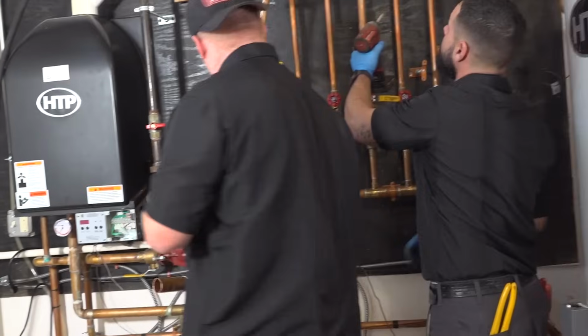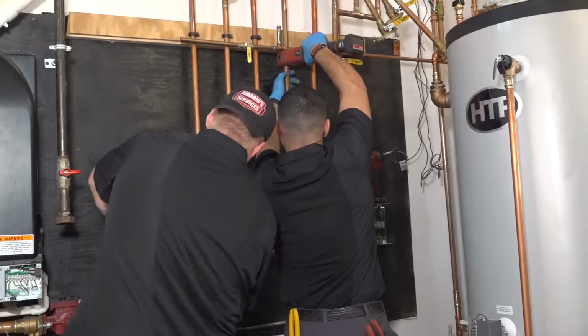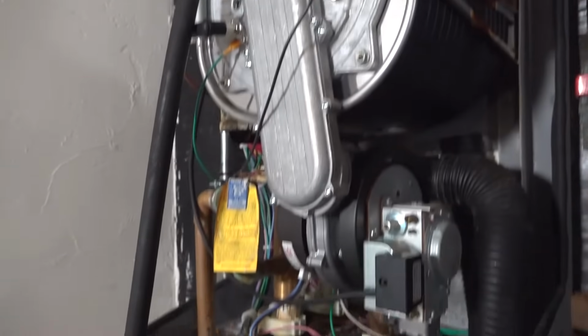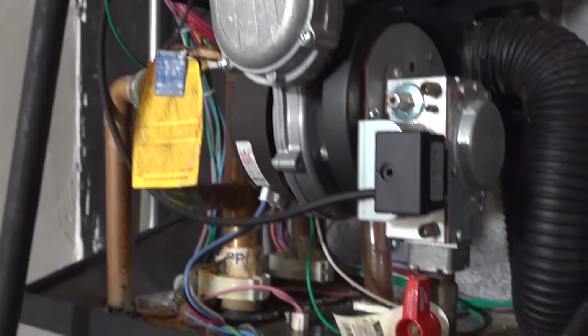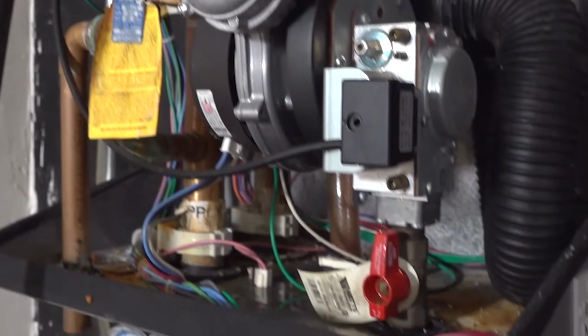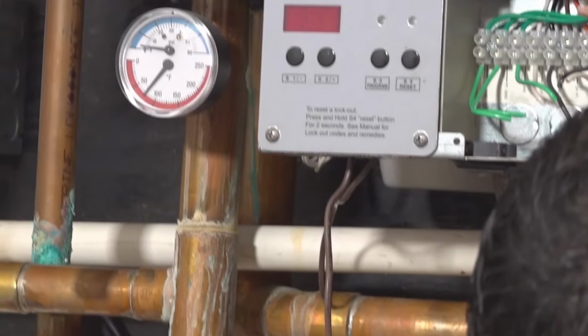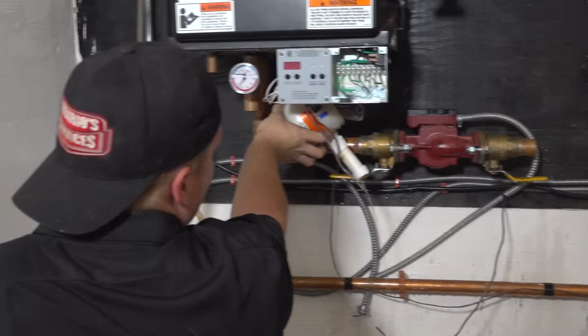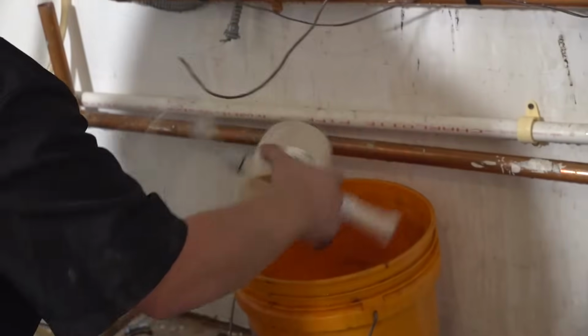Upon going down into our boiler room, Joe and Jim took off the cover for the boiler so that we could just make sure that what was there was efficient, and there was a lot of crud and leaking off the top of the boiler, which also was visible on the pipes coming out of it from the bottom and under the casing of the attachment for whatever was underneath. So just looking at it, once the cover was off, you could clearly see that there was something that needed to be addressed sooner rather than later.